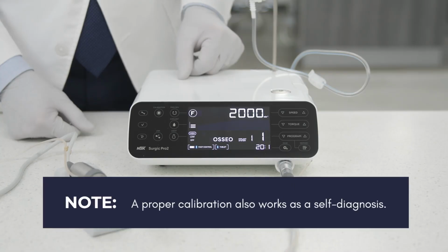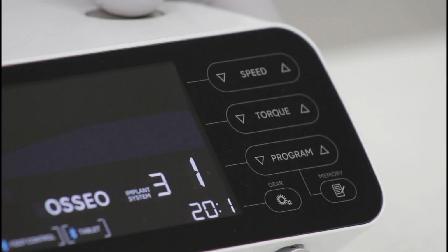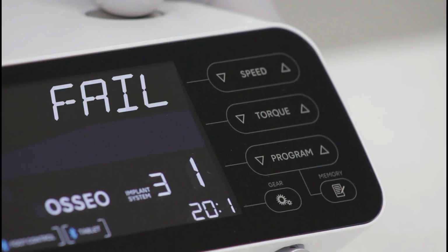Note, a proper calibration also works as a self-diagnosis. If the gears of the handpiece are worn out, correct data cannot be obtained by the system, and fail will be shown on the display at the end of the calibration process, in which case you need to send the handpiece for repair. However, fail could also be shown on the display if the calibration is not done properly and some steps are missed.